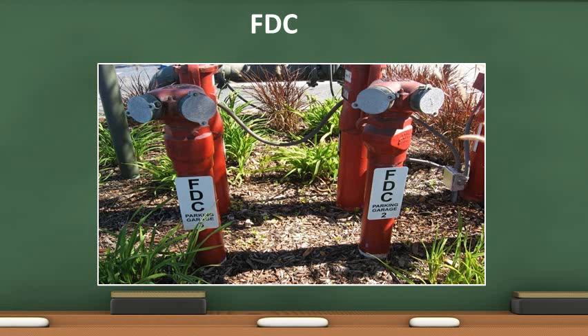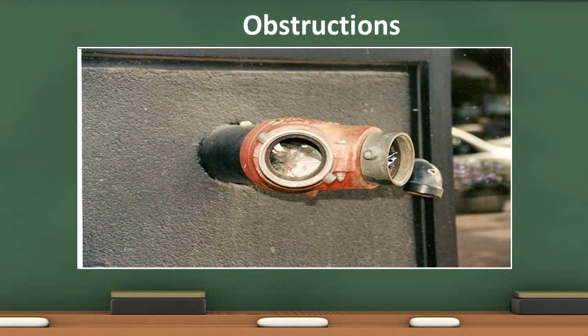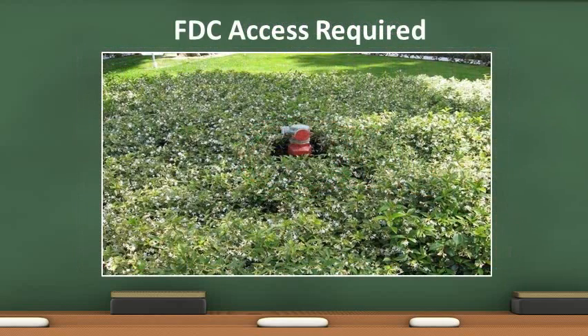Fire department connections allow the fire department to infuse additional water into the sprinkler system, which boosts the pressure to the fused sprinkler heads. FDCs are required to be labeled indicating which buildings they serve. FDC caps must always be in place and no debris inside the inlet. Gaskets are required to be in place and in good condition. Couplings must swivel freely. In this photo, there is no gasket and no cap. If caps are not in place, the interior of the connection shall be inspected for obstructions. When debris is present, the inlets will need to be back flushed. Codes require a fire department connection shall be back flushed every five years.